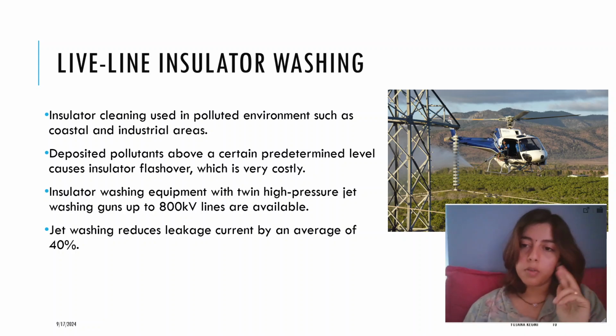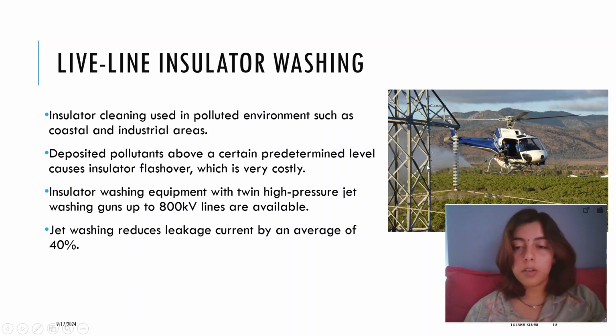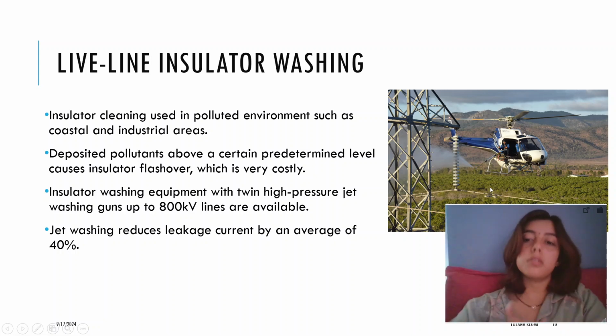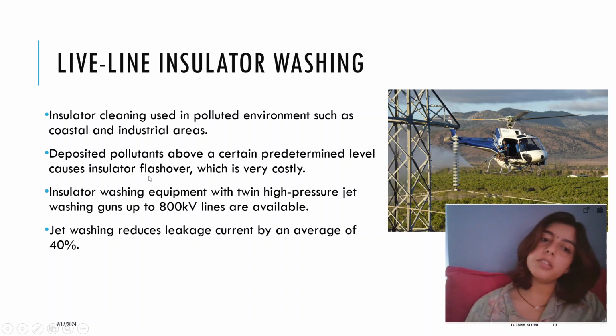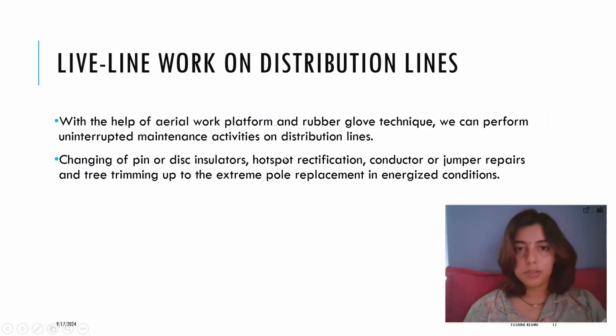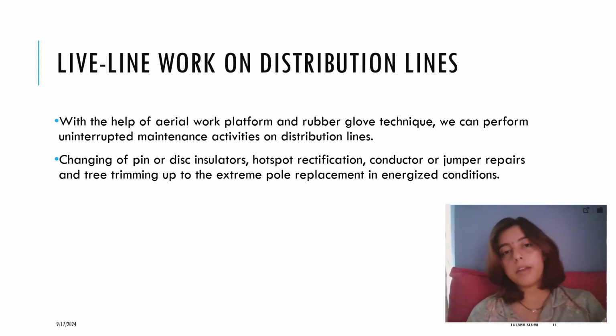So we use a special device called twin high pressure jet washing guns, which is available for up to 800 kilovolt lines. You can see in the picture a person on a helicopter using special equipment and throwing water on the insulator, washing away the pollutants. According to studies, the leakage current is reduced by 40% if you use jet washing techniques. This is one benefit, and one scenario where we use live line working.